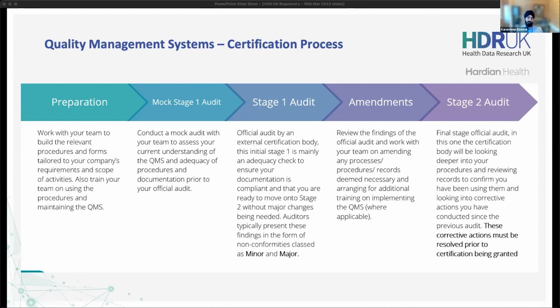So ideally, if you're a medical device and you want to have a CE mark or a UKCA mark, you want to go for a notified body. The last thing you want is to have 1 certification body and then a notified body, because you're effectively paying twice for the same thing, more or less.